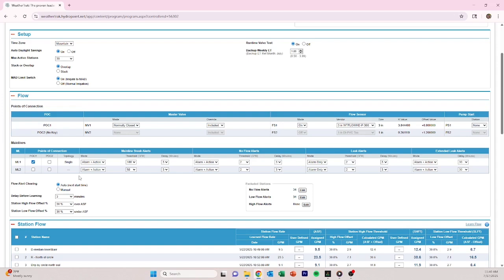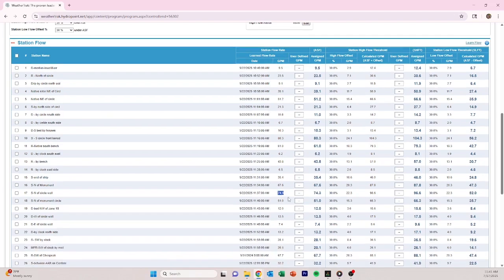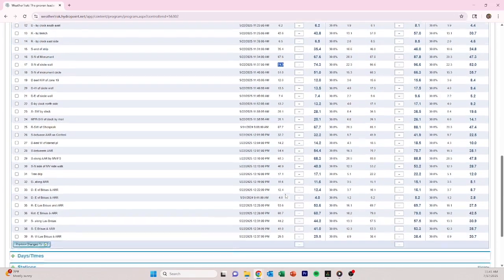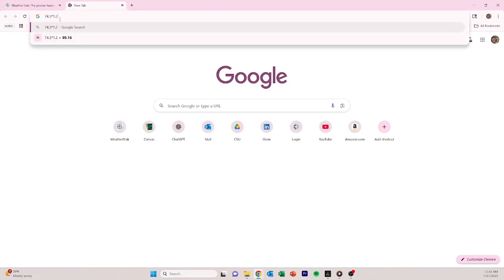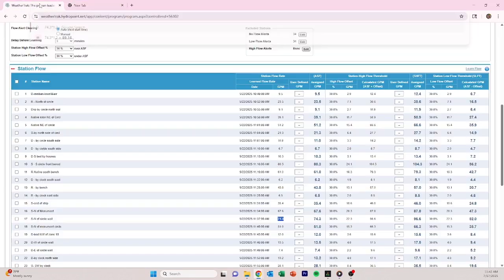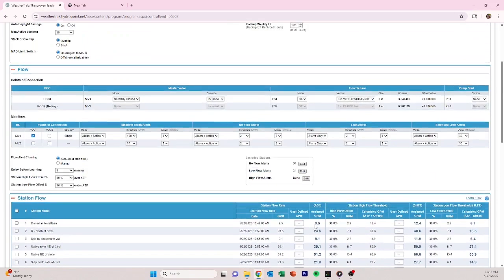We want to set this value 15 to 20% higher than the highest anticipated use case for the controller. The next step that I take is looking for the highest value flow rate in our gallons per minute column of our table, which on this controller is 74.3 gallons per minute. So, I'm going to take this number and multiply it by 1.2 to get 89.16 gallons per minute. This shows us our value that is 20% higher than our highest anticipated use case.